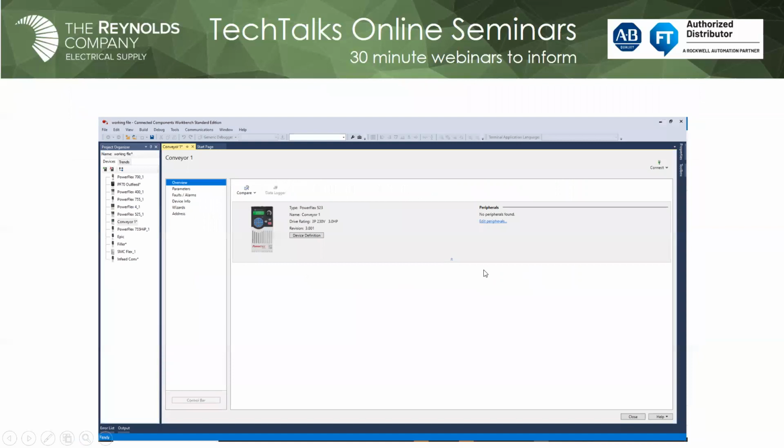Okay, Mark. So here's a screenshot of a quick project I threw together. If you use Drive Standalone, this is the software that you want to use. If you're using drives over Ethernet with the Logix controller, the software will still look familiar because it's embedded into 5000. But here's Standalone. Just say I have a line, let's call it W line. I've got this enclosure and I've got these 12 VFDs in that enclosure.